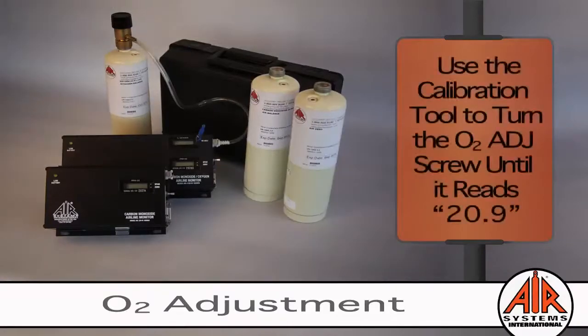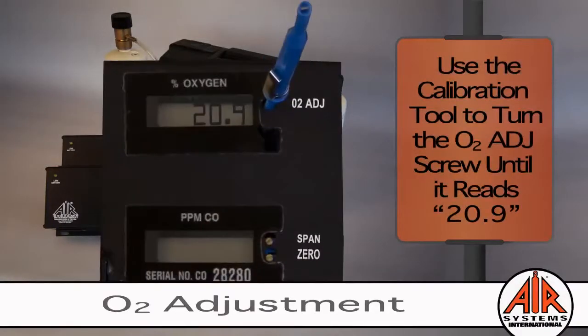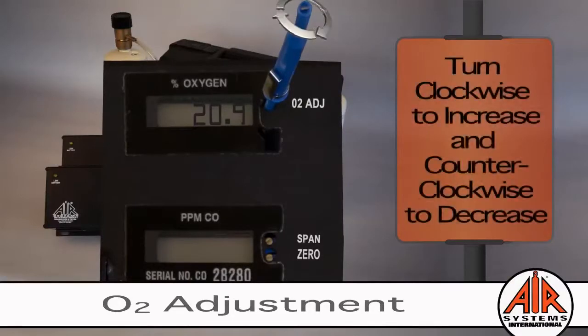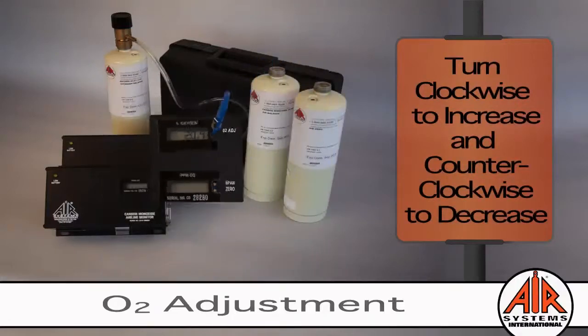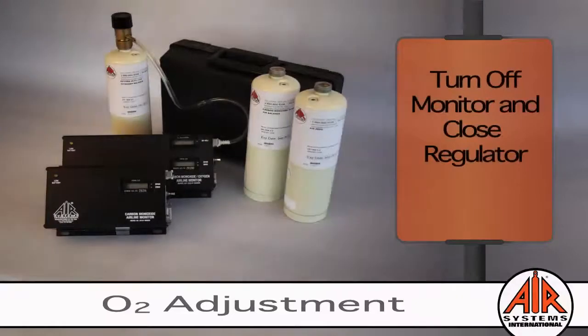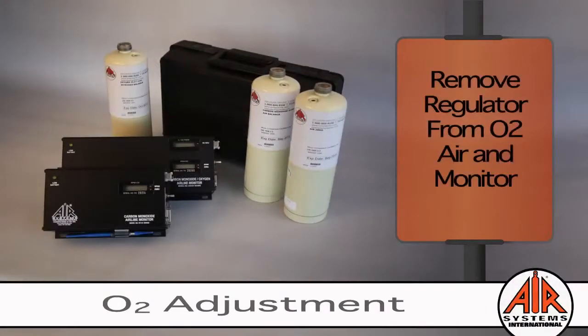Use the calibration tool to turn the O2 adjusting screw until it reads a value of 20.9. Turning clockwise to increase the values and counterclockwise to decrease the values. Turn off the monitor, close the regulator, remove the gas tube. Your calibration is now complete.